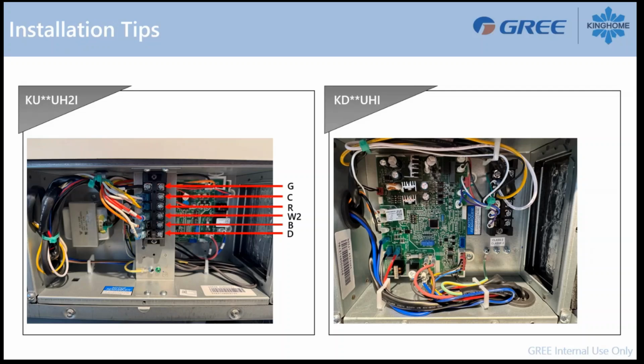If we take a look at the connection, they use the same terminal board here. So the first one is your G connection to start up the fan. You will have just below your C and R to power up. This is your 24 volt power right away here. So your common and your power on R.